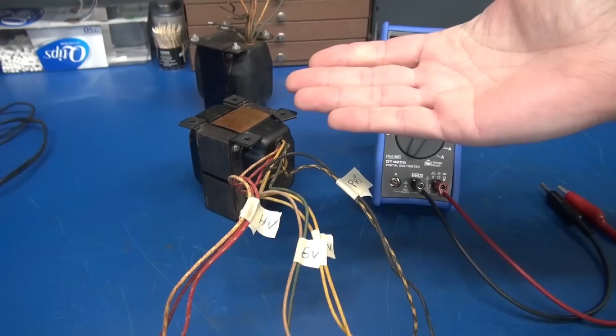My meter is set at ohms, 0 to 600 ohm scale. There is my primary, about 7.7 ohms. Here is the 5 volt winding, very low. My 6 volt winding, same thing, low resistance. Now the high voltage winding is between the 2 reds. You see about 177 ohms. If I go from one of the reds to the center tap, this can be half of that value.